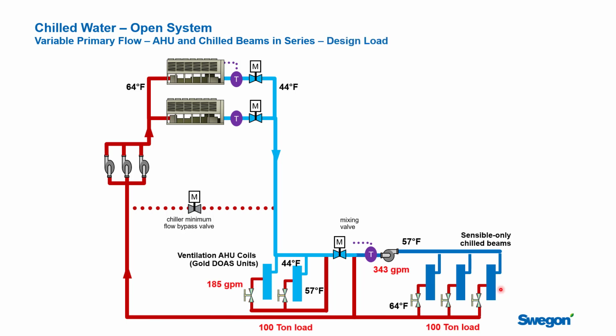So I want to put flows on. We saw that the temperatures just worked great, but let's put the flows on, right? So we're going to say we have a 100-ton load here and a 100-ton load here. And to meet that 100-ton load, 50 tons in our 2 air handling units, to heat that water from 44 to 57 will require 185 GPM. Straightforward calculation. So we're going to run that water through the 2 coils. We're going to heat that 185 GPM from 44 to 57. So by the time I get in this pipe right here, I've got 185 GPM of 57 degree water. Now set that aside for a second.